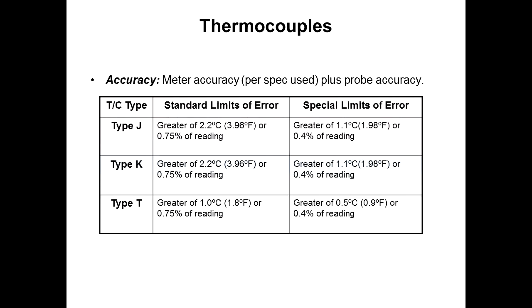These are 3 commonly used thermocouples: Type J, Type K, and Type T. Type K is the most common. For those looking for extreme accuracy, you can see that the accuracy is not great on either one. Special limits of error wire has pretty much twice as good accuracy as standard limits of error. The difference is that the alloys used to make the wire are purer. They're more highly refined alloys, so that's the reason for the better accuracy. It just costs more, but it is a much better accuracy unit.